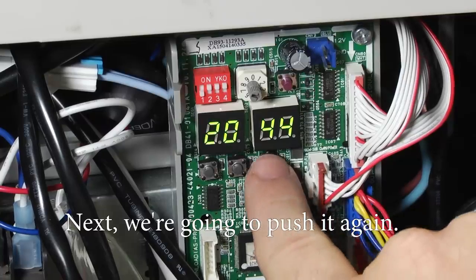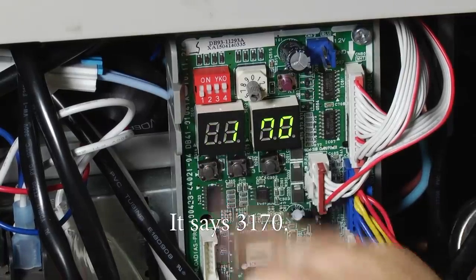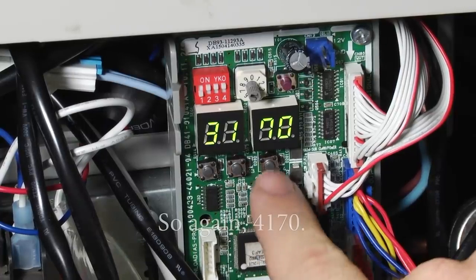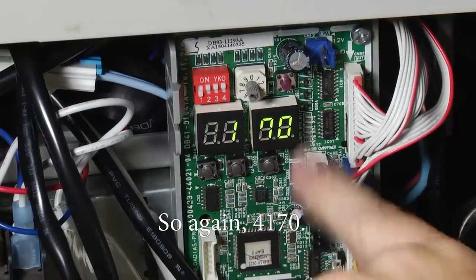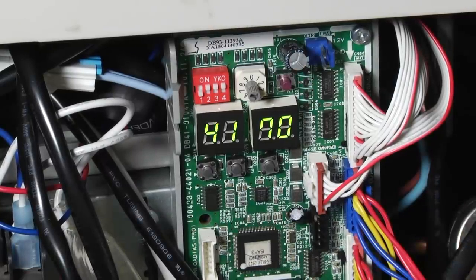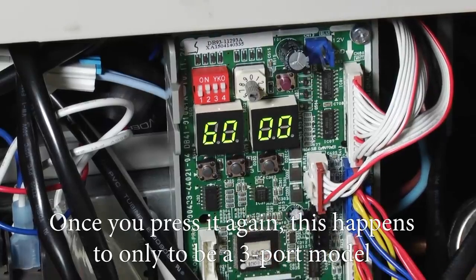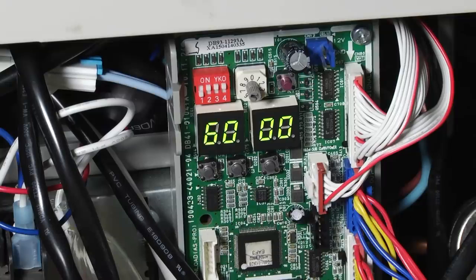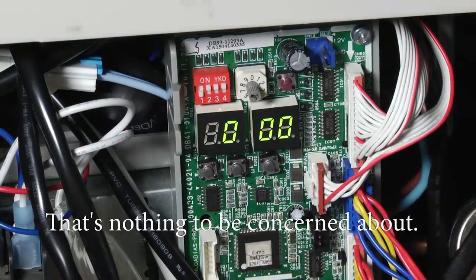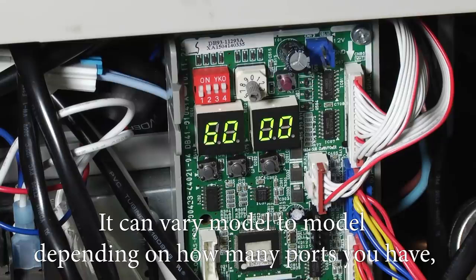So next we're going to push it again. And it says 3170. That is actually your current EEV steps for port A. So again, 4170, that's your current steps for EEV B. Press it again, and that's your current steps for EEV C. Once you press it again, this happens to only be a 3-port model, so we're going to have all zeros there. That's nothing to be concerned about. It can vary model to model depending on how many ports you have. You may get zeros on a couple of these pushes.